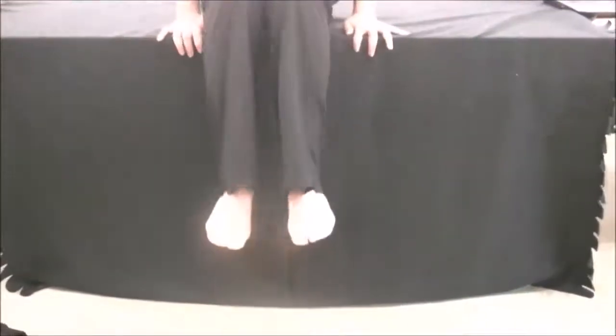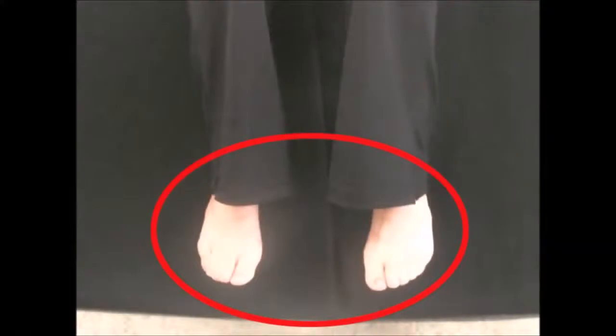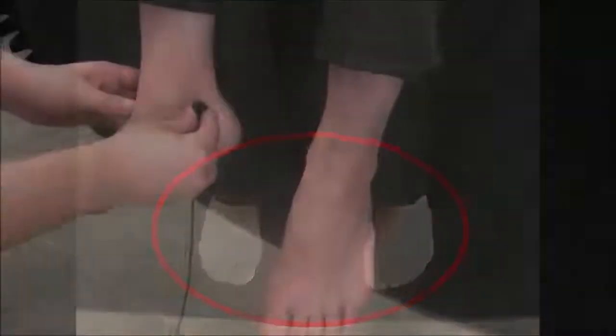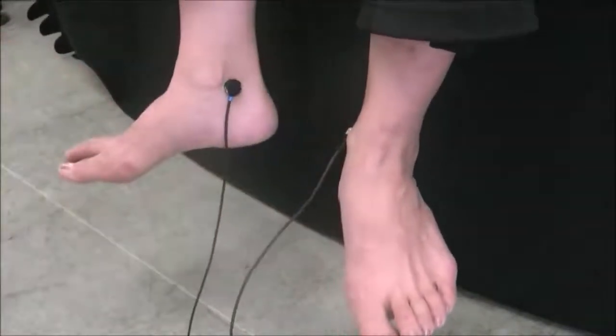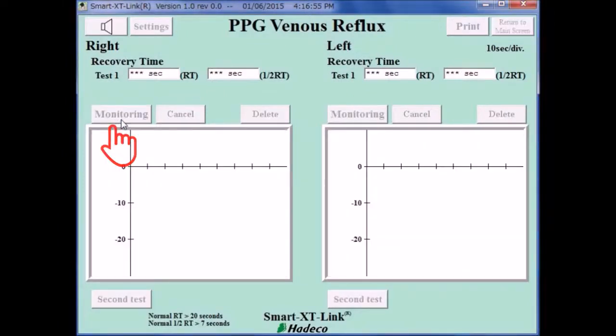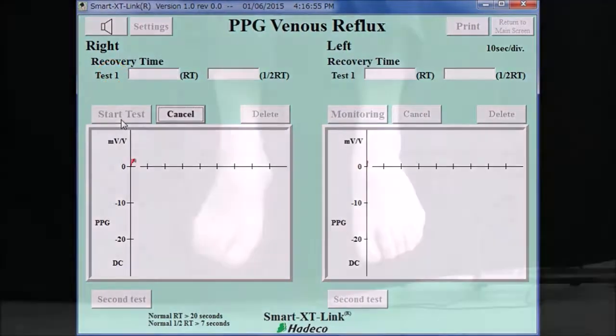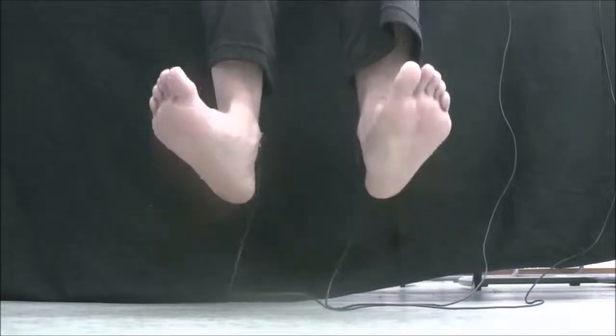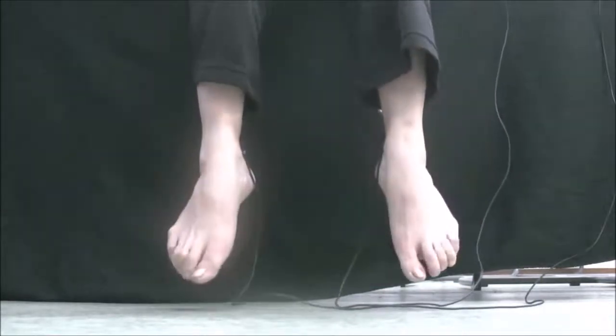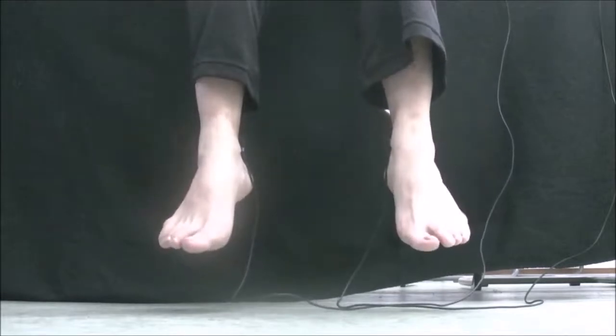Click the sound icon to adjust sound volume for the XT. Now, let the patient sit on an examination table so that the feet are off the floor. Fix the PPG transducer over the malleolus with the tape like this. Click Monitoring to start monitoring the waveform. When the waveform becomes stable, click Start Test to start the venous reflux study.